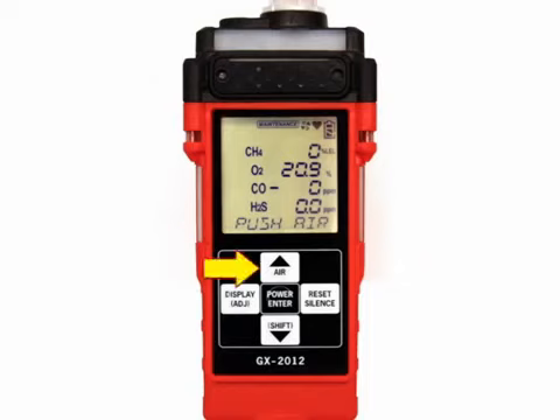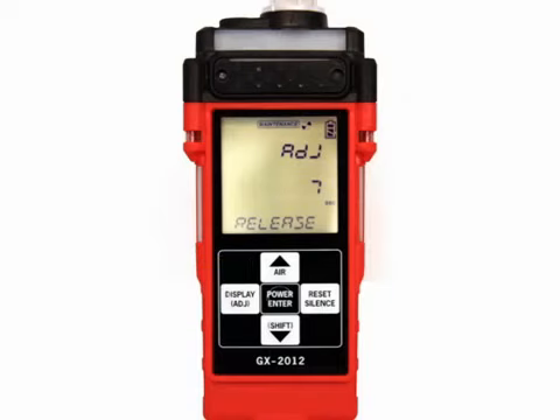Press and hold the Air button. The LCD prompts you to continue to hold the Air button. Release the Air button when the Release message is displayed. The unit will take a few seconds to adjust the fresh air readings, then indicate End at the bottom of the screen and return to the AirCal screen.